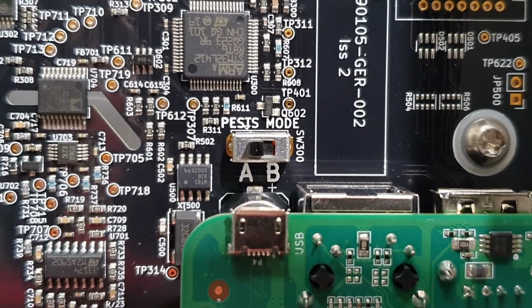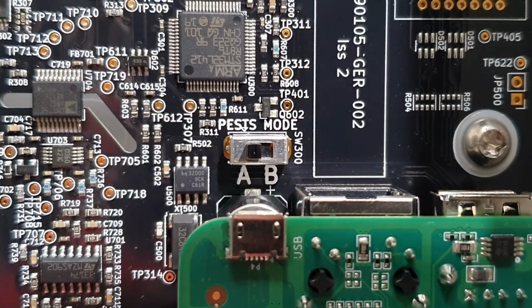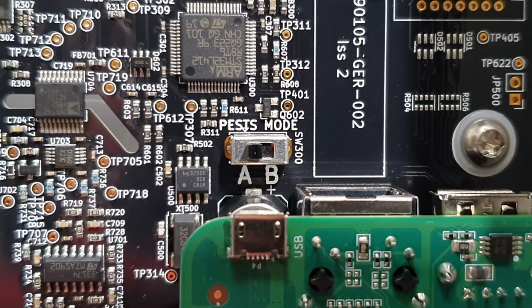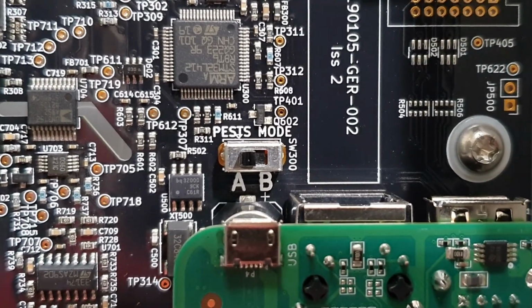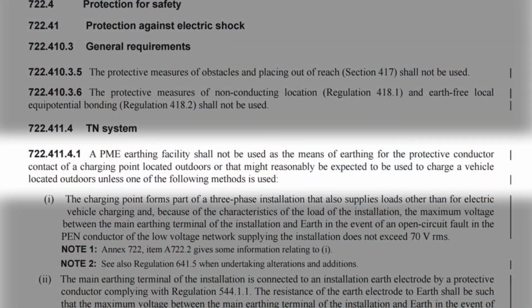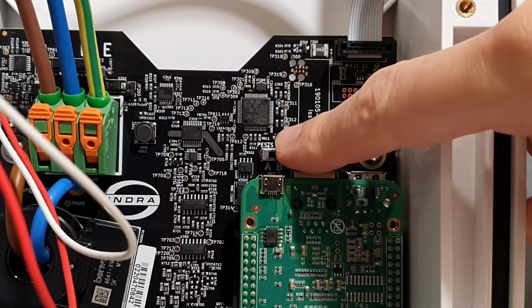Now this is nothing to do with mode 1, 2 or 3 charging or anything like that. It's to do with how the requirements for regulation 722.411.4.1 are met. As stated earlier in the video, that regulation reads: a PME earthing facility shall not be used as the means of earthing for the protective conductor contact of a charging point located outdoors or that might reasonably be expected to be used to charge a vehicle located outdoors unless one of the following methods is used. First of all, we need to bear in mind that this is referring to a TN-C-S system using protective multiple earthing. Therefore, if you're connecting to a TN-S or TT system, then you don't need to apply any of the indents that follow. And critically, the switch on the charger PCB must be set to mode A.